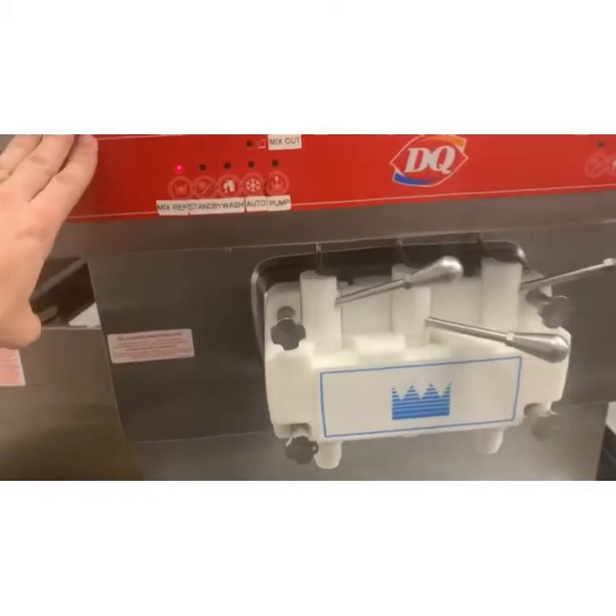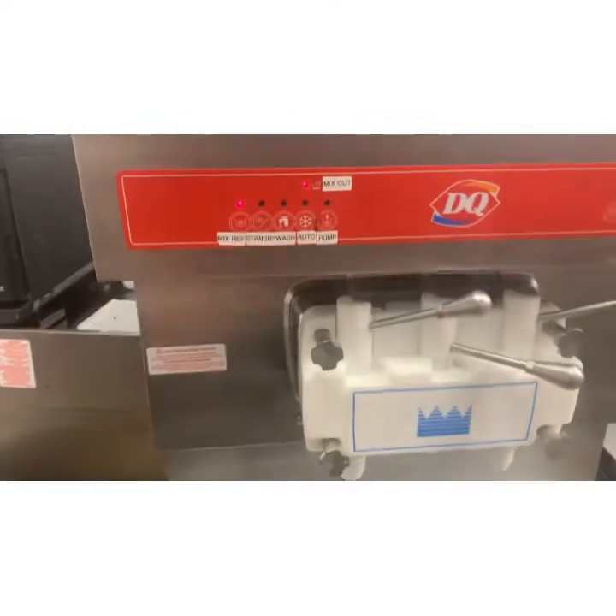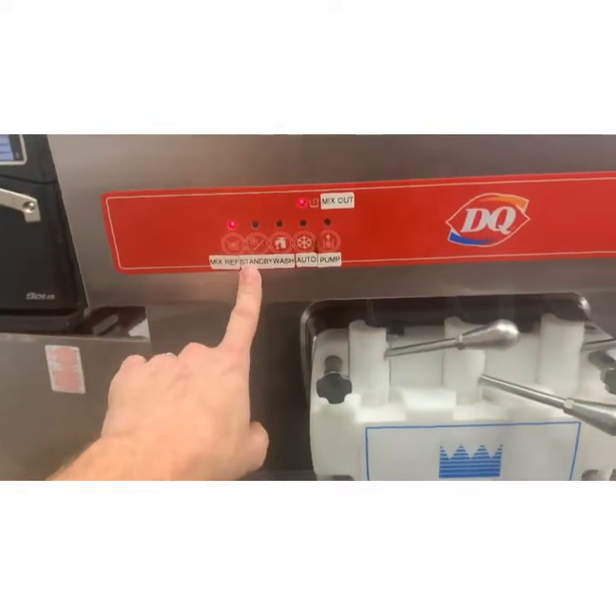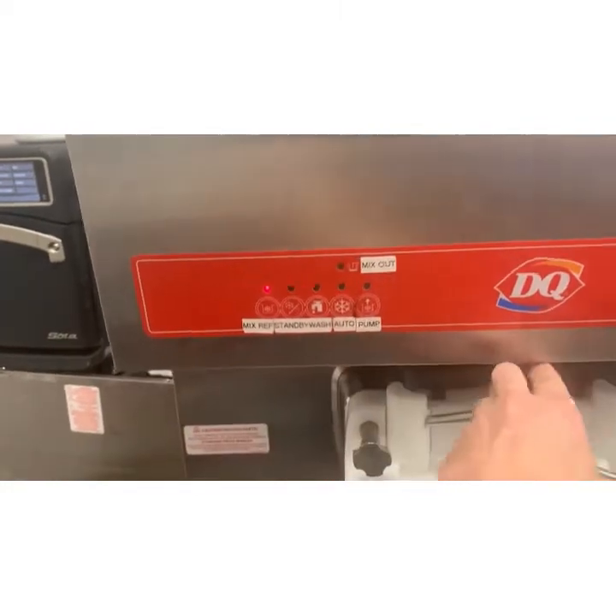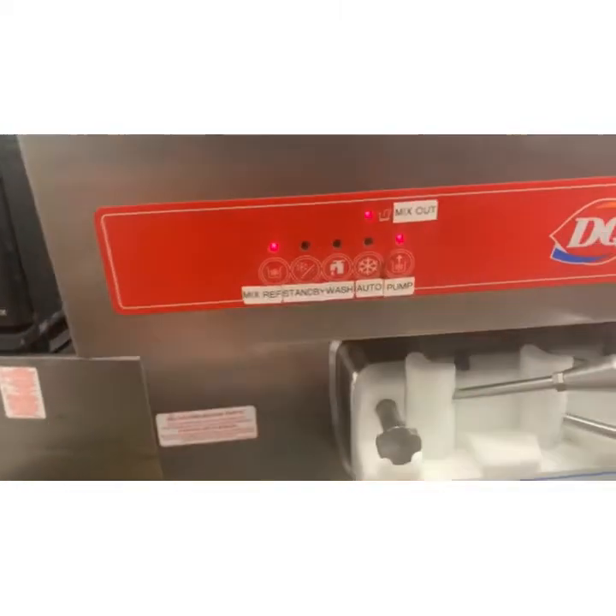Alright, so this is a Taylor ice cream machine. The left side, from the time they built it this morning, won't operate. It says mix out even if you manually try and run the pump.